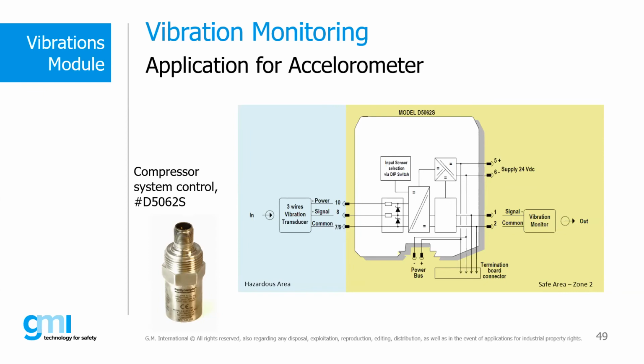It provides a fully floating DC supply for energized vibration transducers, accelerometers, or 2-wire sensors located in a hazardous area, and repeats the sensor input voltage in a totally isolated circuit located in the safe area, to drive vibration monitors or analyzers for rotating machinery control and supervision purposes. GMI can supply devices to isolate and power the different types of sensors present in industrial automation and beyond.